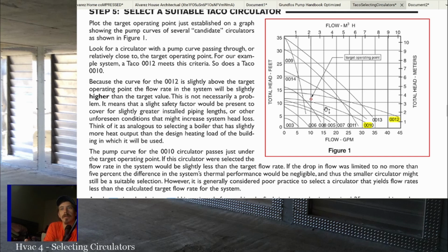Think of it as selecting a boiler that has slightly more heat output than the design heating load. If we need 40,000 BTUs, we're probably not going to select a boiler that outputs exactly 40,000 BTUs. We're allowed to size up to 35 or 40% over on them. So we're going to select something that's got a little bit of extra heat output. And that's acceptable with gas appliances, but that's another class.